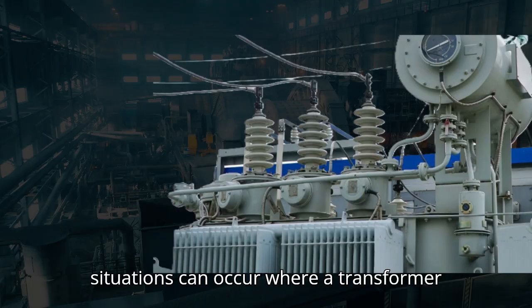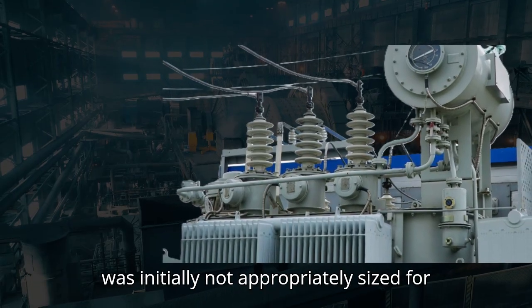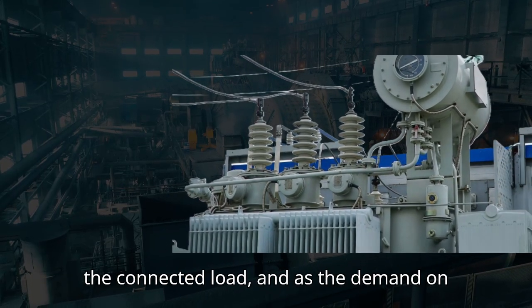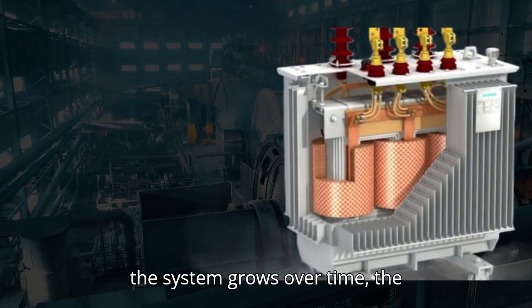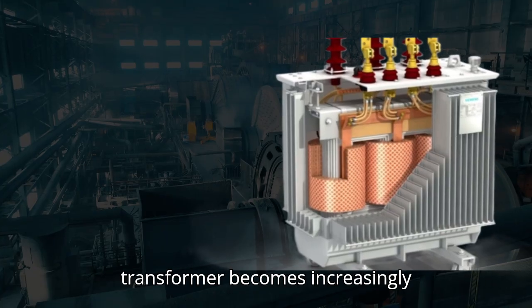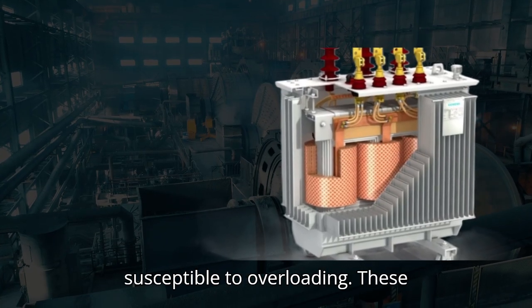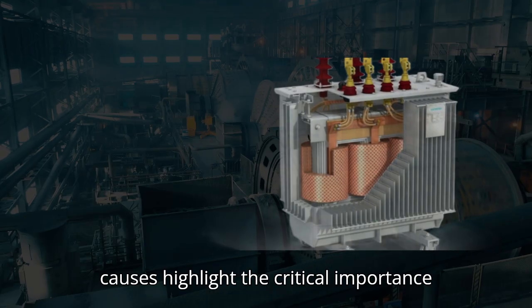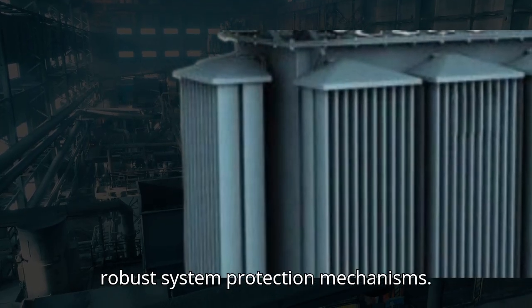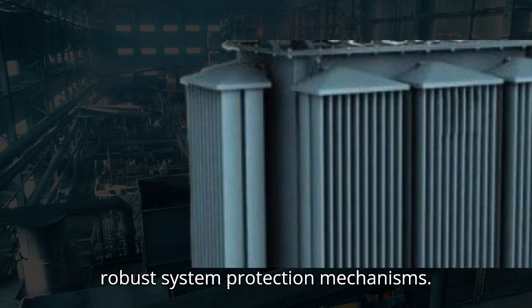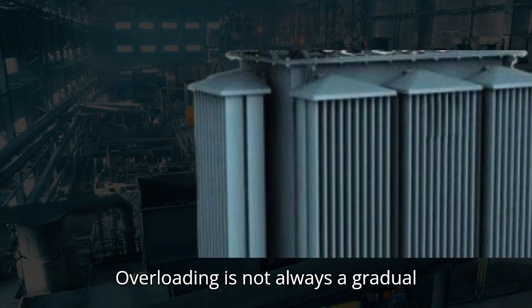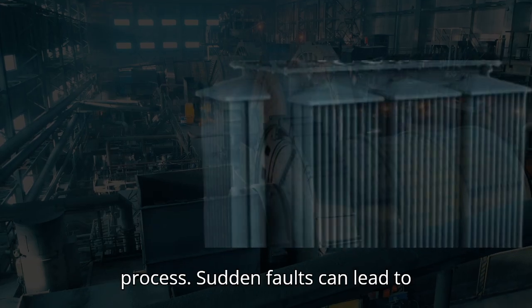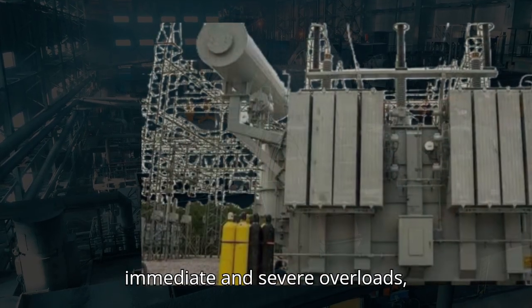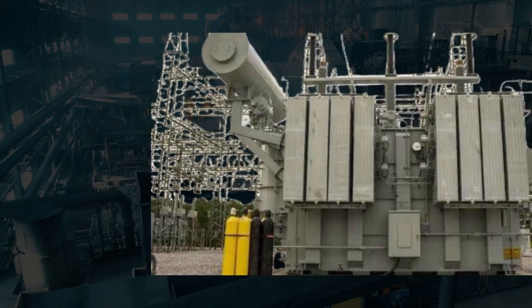Furthermore, situations can occur where a transformer was initially not appropriately sized for the connected load, and as the demand on the system grows over time, the transformer becomes increasingly susceptible to overloading. These causes highlight the critical importance of both accurate load forecasting and robust system protection mechanisms. Overloading is not always a gradual process. Sudden faults can lead to immediate and severe overloads.